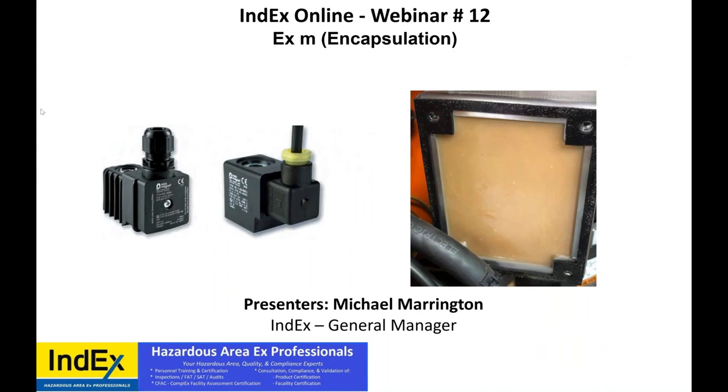Okay. Index Online, webinar number 12: EXM, encapsulation. So what are we talking about? We're talking about pieces of equipment that have some type of encapsulant that has been poured and dried inside of it, and it acts as a means of keeping hazardous atmospheres out, dissipating heat, and making the equipment safe for use in hazardous areas. By the way, these are solenoids. This is a terminal box that has now been turned into an EXM terminal box. So let's jump into it.